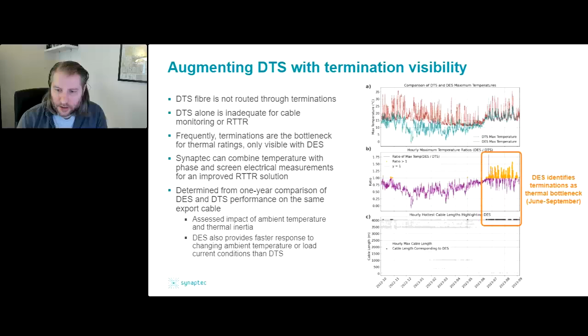So in our Greenlight systems, by standard, we would actually include DTS in our offering. Again, we're getting the best of both worlds. We get the usual benefits from DTS and a typical RTTR approach, but we can add intelligence from our sensors. Simply by putting temperature sensors effectively at the termination, we can close off another gap and provide basically a full RTTR system that's looking at the whole cable and all of the accessories. That's effectively an enhanced RTTR system that we have developed.